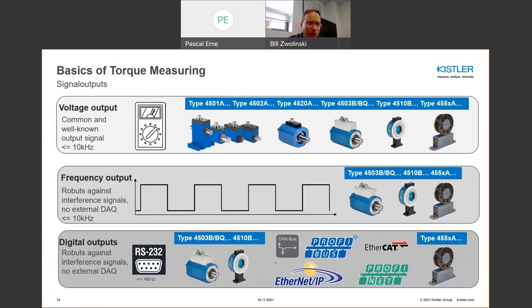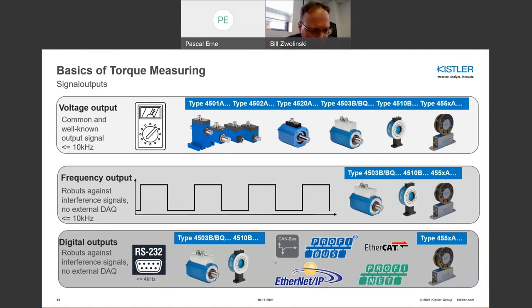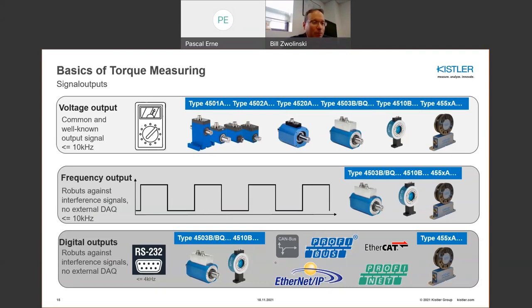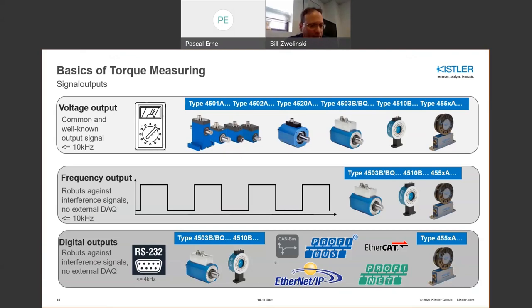The voltage output is likely the most popular output type because it interfaces to nearly any data acquisition system. The wide bandwidth of strain gauge-based torque meters is quite impressive — a 10 kHz bandwidth is actually quite useful for many applications. When you have rotating test articles with several blades, the rotating speed is a fundamental frequency, and you multiply that by the number of blades to get the true frequency rate, with harmonics on top of that. So rotating equipment absolutely requires attention to how much frequency you might really need. Torque meters need to be considered in that regard based upon the application.